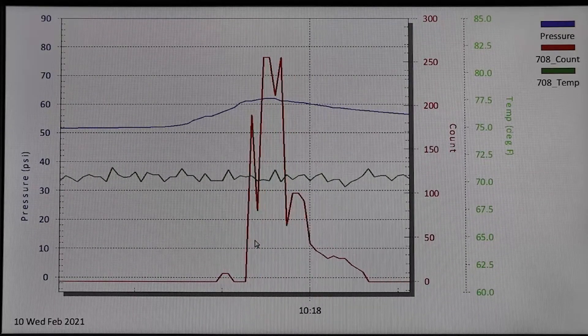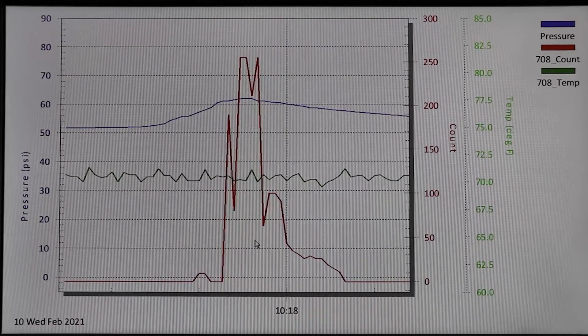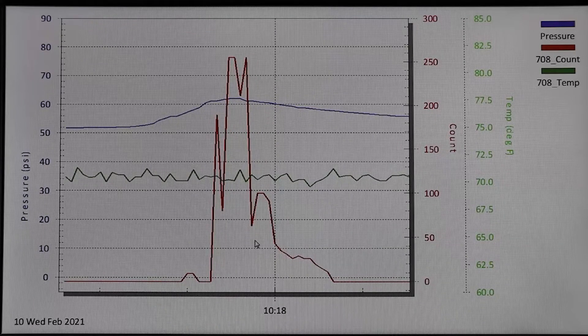Approximately 40 seconds later the system pressure begins to increase further and as it reaches the valve set pressure and begins to lift the acoustic count begins to increase. As the event is ending the system pressure decreases as well as the acoustic signal count and the system reaches a safe and steady state with the valve closed and the system pressure normalized.